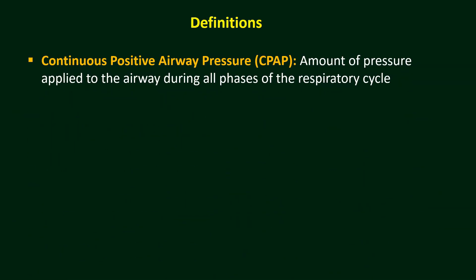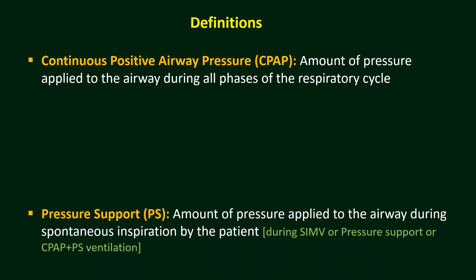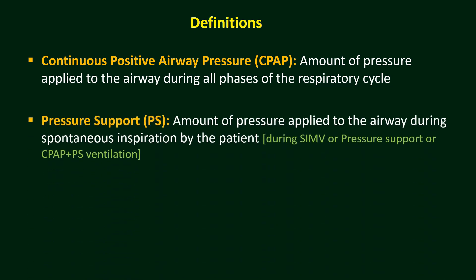Continuous Positive Airway Pressure, CPAP, is the amount of pressure applied to the airway during all phases of the respiratory cycle. This is somehow synonymous to PEEP or positive end expiratory pressure. Pressure support is the amount of pressure applied to the airway during spontaneous inspiration by the patient, used in SIMV mode, pressure support mode, or CPAP plus pressure support mode of ventilation, which we shall see in subsequent lectures.